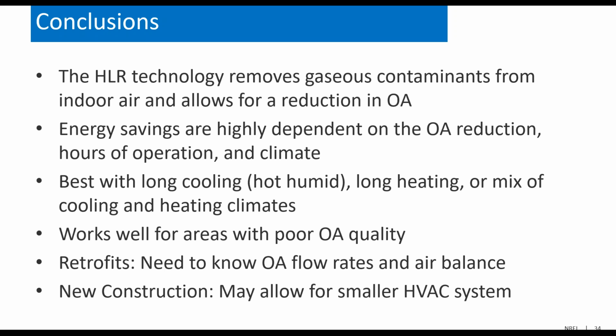In a retrofit application it can work well, but you really have to know your outside air flow rates and the air balance in your system and be able to control those things. That's a challenge in a lot of existing buildings. Maybe a dirty little secret, but most buildings have poor ventilation and poor indoor air quality. This is challenging for buildings, for sure.